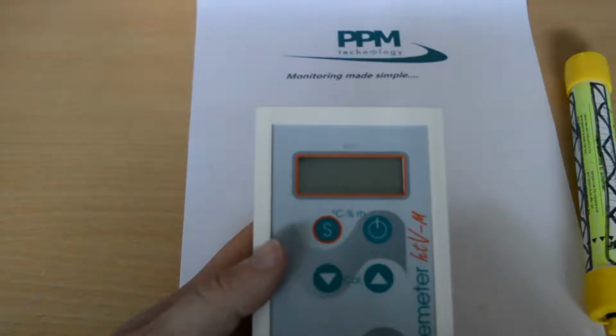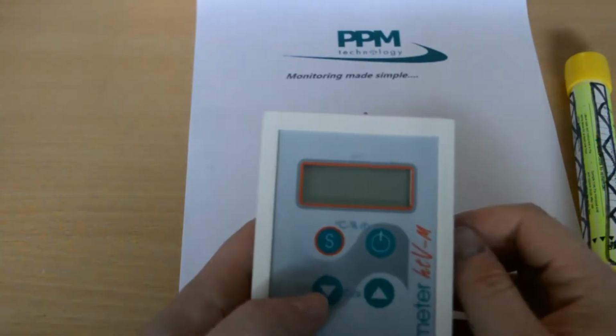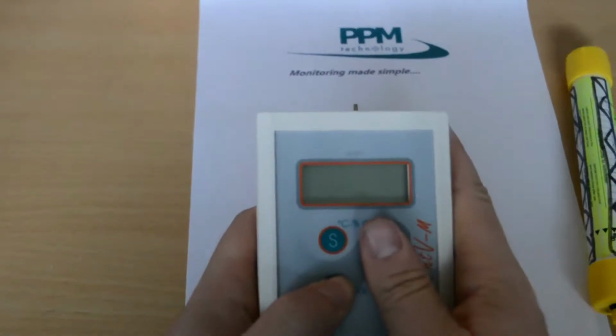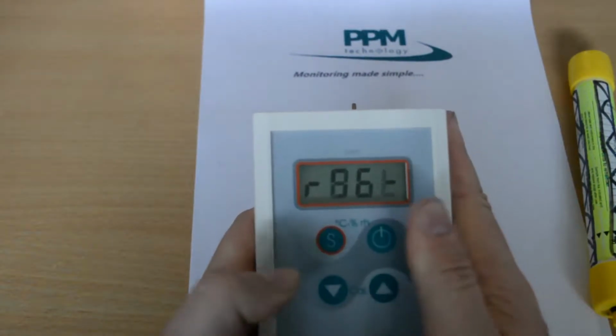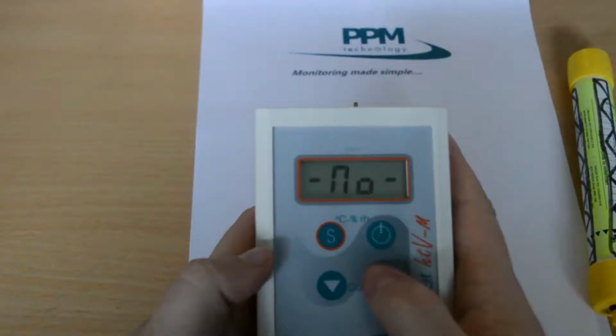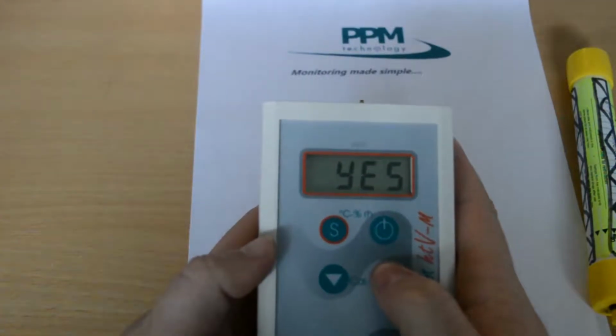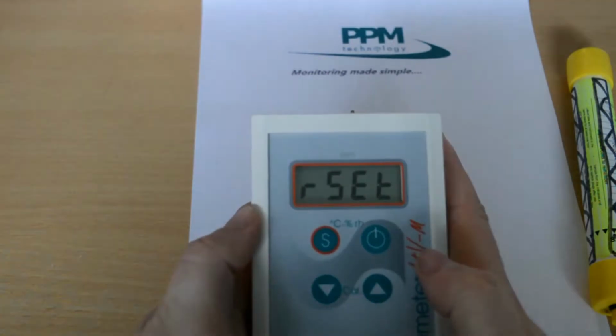Performing a reset of the instrument. Make sure that you have a valid calibration standard to hand before performing this procedure, as your current calibration will be deleted and there is no way of undoing the reset once it has been completed.